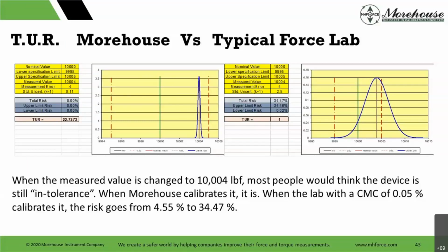So when we look at that general expectation, and they're using the accuracy spec again, not the uncertainty, and you say, I want a conformity assessment, that other lab has to fail your device. They don't really have to fail it. They can call it an indeterminate pass or an indeterminate fail. They can give you the binary decision rules that G8 allows you to do, but that's not a pass. An indeterminate pass, an indeterminate fail is not a pass. And people need to get with that and understand that.